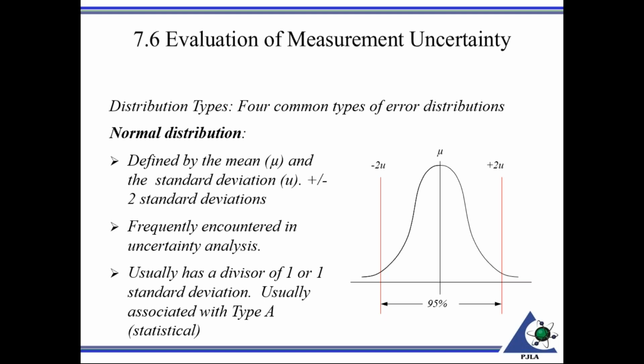95% of the data points would be between the mean plus or minus 2 standard deviations. So this is typically encountered with uncertainty analysis, particularly with repeatability studies. Has a divisor of 1. And this is statistical, which is a type A analysis.